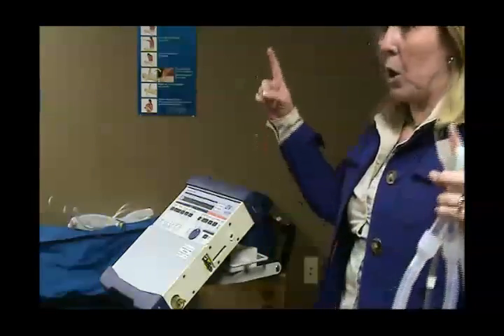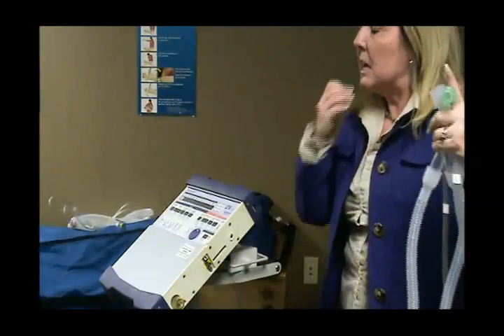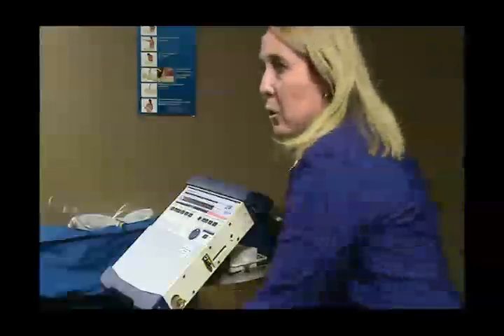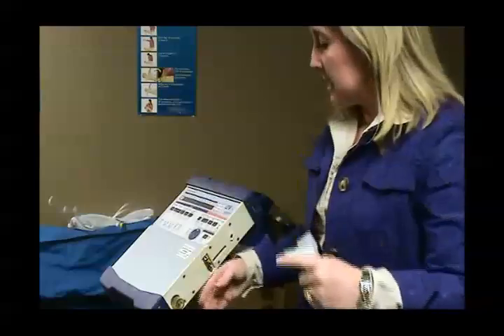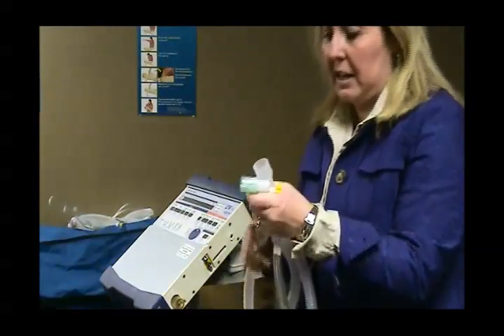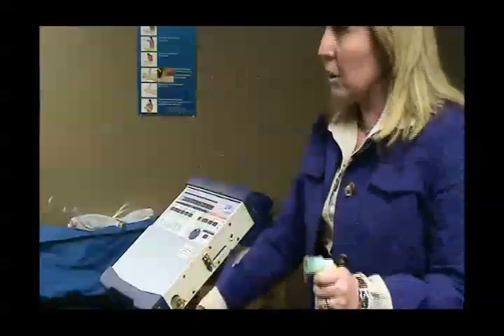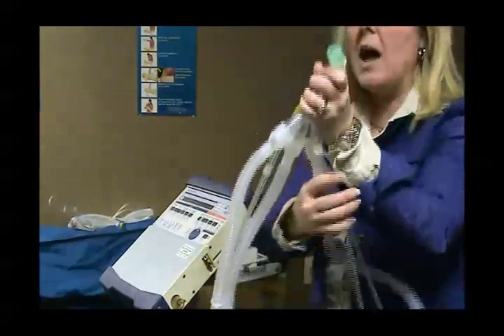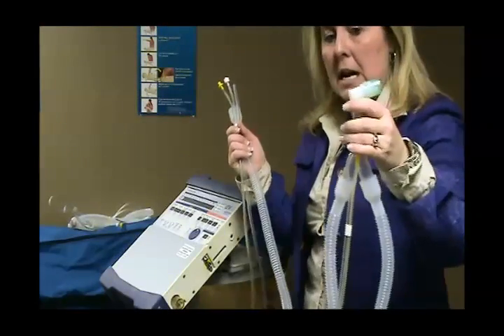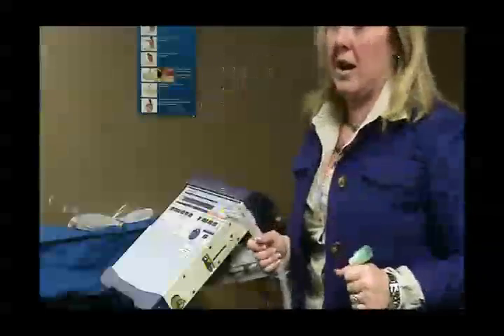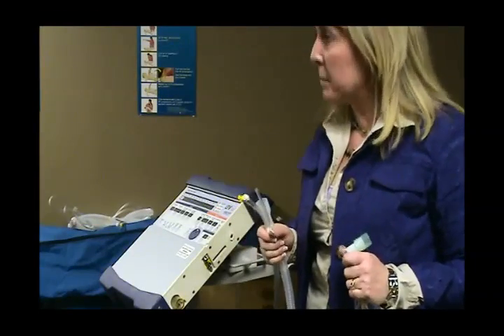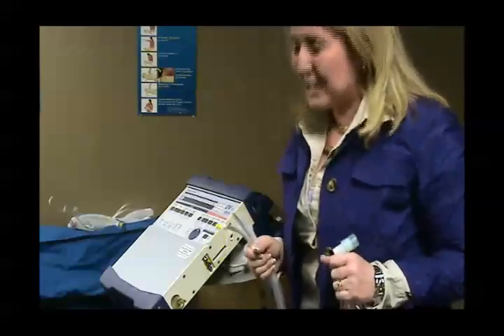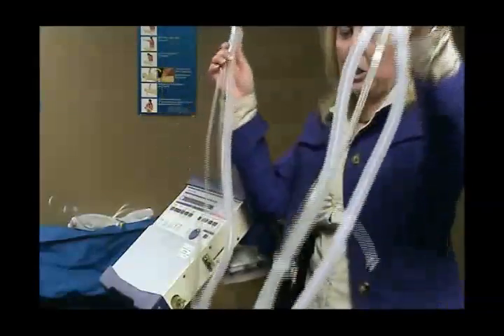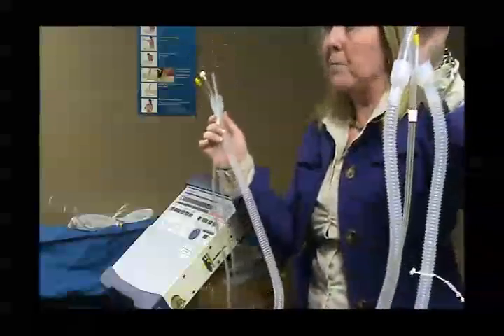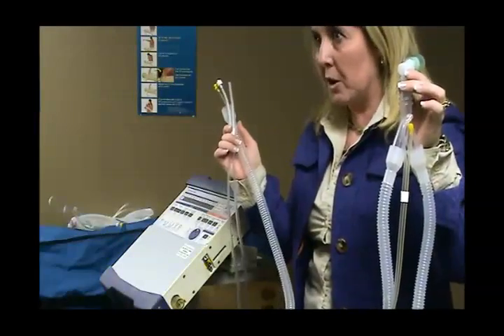So inside the package, there will also be a little short tubing about like that. If you are using it with a heater, a water heater, you need that piece, right? Because that's the piece that goes from the vent to one side of the heater chamber, and then this one goes on the other one. If you're using it on a dry circuit with an HME, does everybody know what HME is? Heat moisture exchanger, okay? Then you don't need that little piece. Throw it away, okay? Because someone is going to try to figure out how to make it fit in line with something, and they're going to mess something up, okay? So if it's with a dry circuit like this, no water chamber, pitch it, okay? It's just going to cause you trouble if you don't.